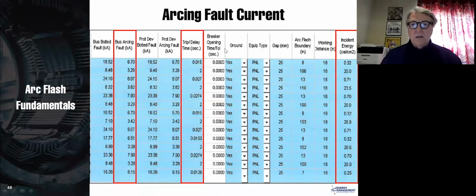Let's take a look at these top two lines. This is a real job. On this particular circuit, we have 18,000 amps of fault current, but that is the bolted fault current. If there is an arc, there's an impedance in the arc, and therefore the arcing current is going to be less. The arcing current on that circuit is 6,700 amps. It will trip in 0.015 seconds, and our calories is 0.32. So at 0.32, all we need to wear is just shirt and pants that are non-flammable.